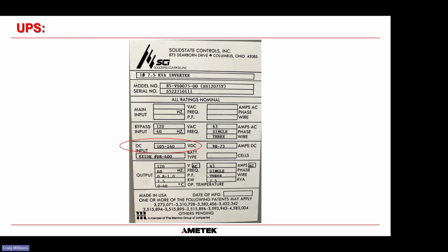And then even for our UPS systems, this is for an older AMETEK solid-state control UPS system. This is a 7.5 kVA inverter, to be exact. And what our inverter is designed to accept is 105 to 160 volts DC, okay? So the battery has to be designed to work within those parameters.